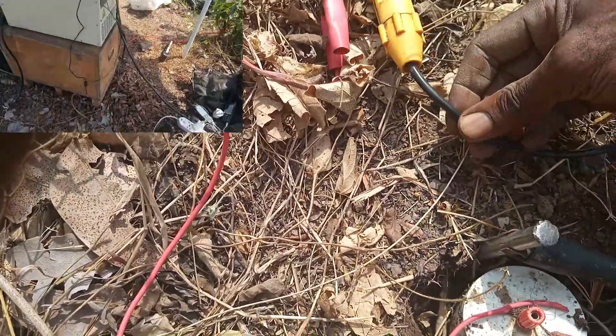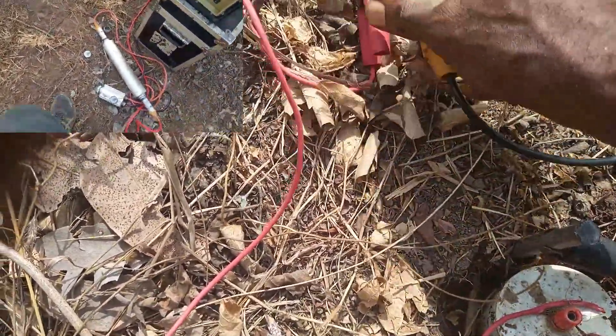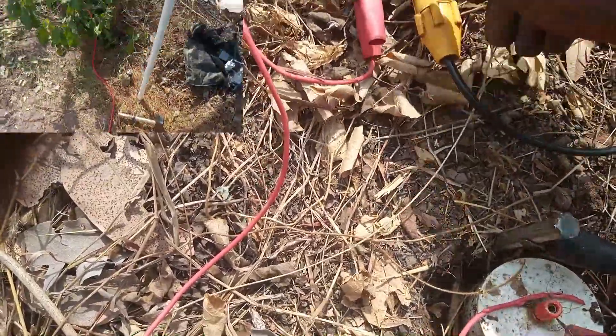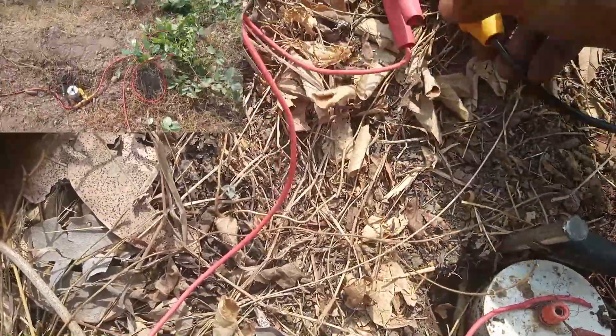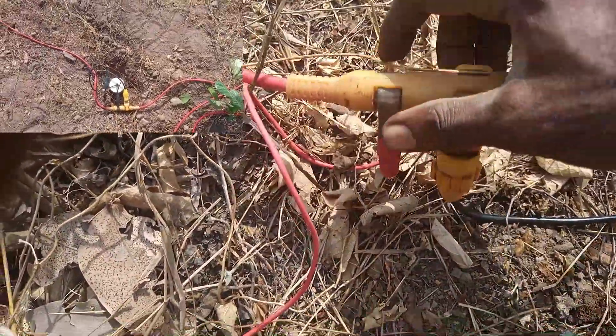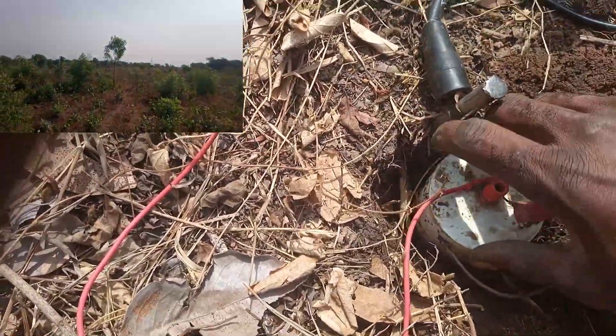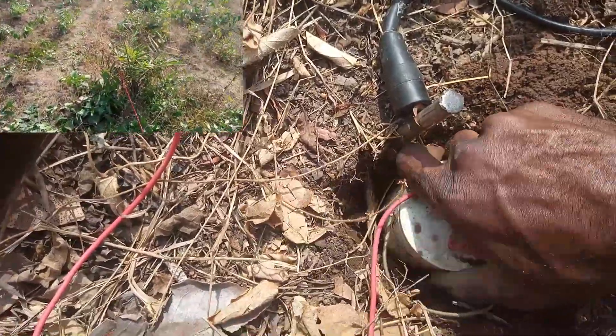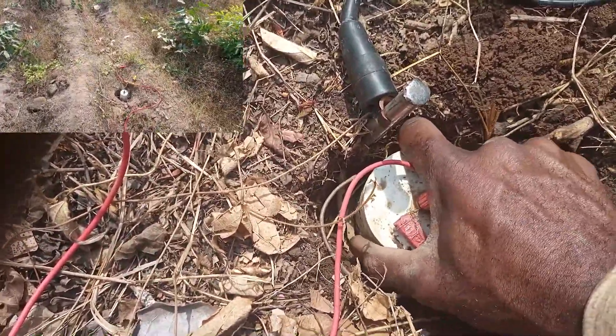Coming here, this is for the power. The cable here is bigger — this is the sender and this is the receiver. The actual sender is P1 and P2. Make sure the contact here is okay, the grip is there, and also here the grip is there. Having done this, make sure this is firmly grounded.